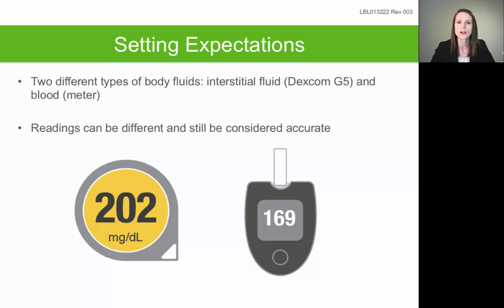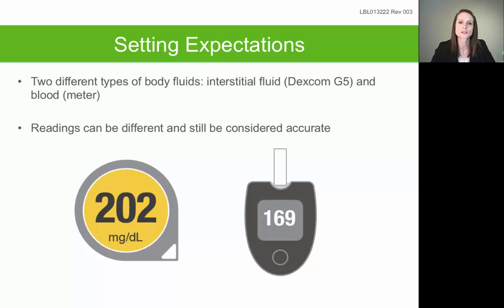Sometimes they will be the exact same number, but more often than not they will be close or similar. If you check a finger stick value and you get a value that is 80 or less, your Dexcom should read within 20 points. But if you check a finger stick value that's over 80, your Dexcom should read within 20%. For example, if you check a finger stick and get a value of 90, 20% of 90 would be 18, and you should expect to see a Dexcom value within 18 points of that 90. Or if you get a value of 70, you should simply see a Dexcom reading within 20 points of that 70.